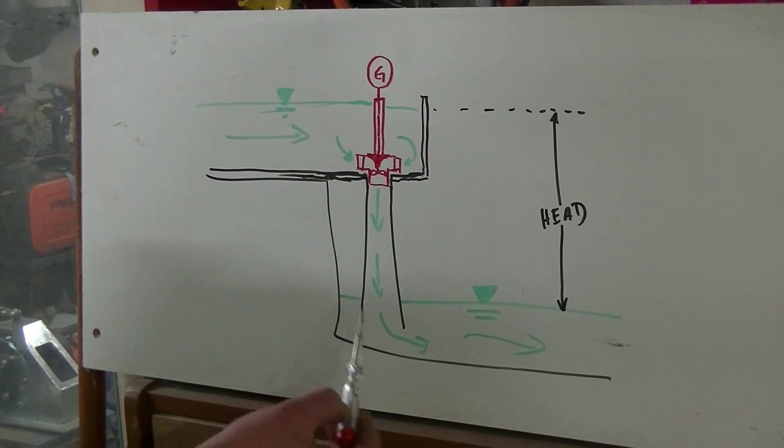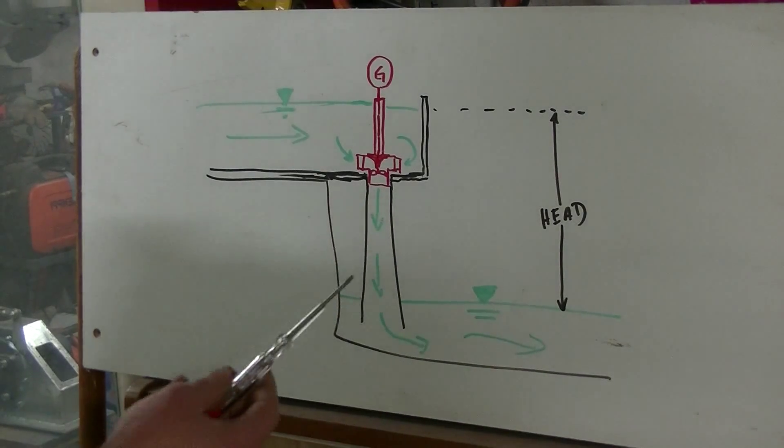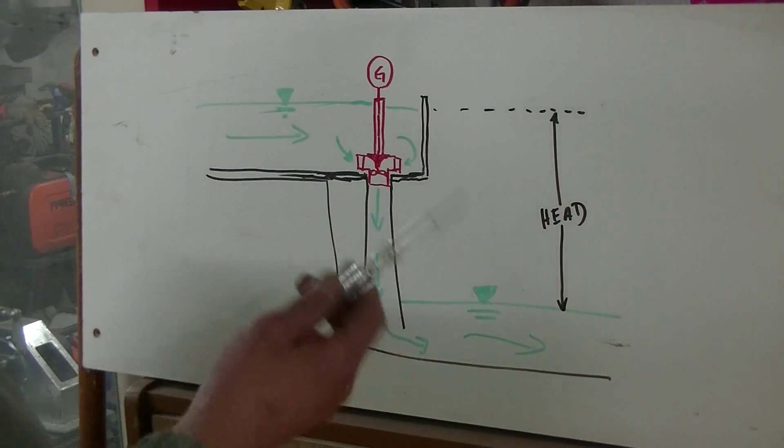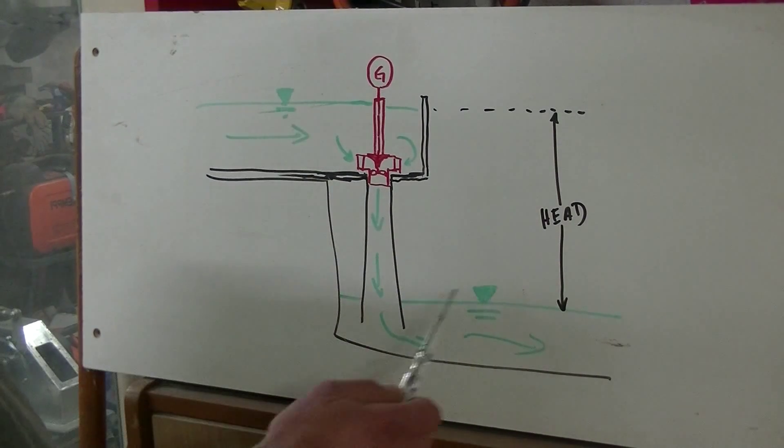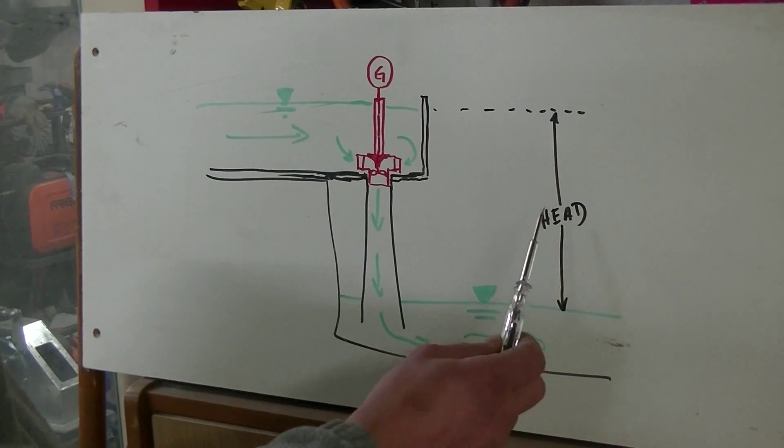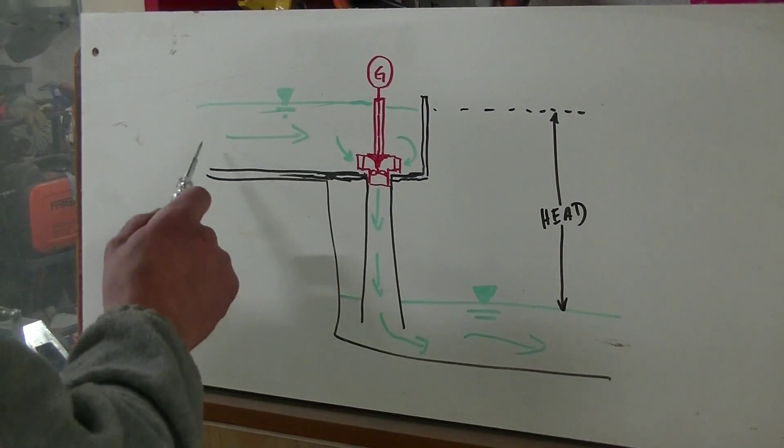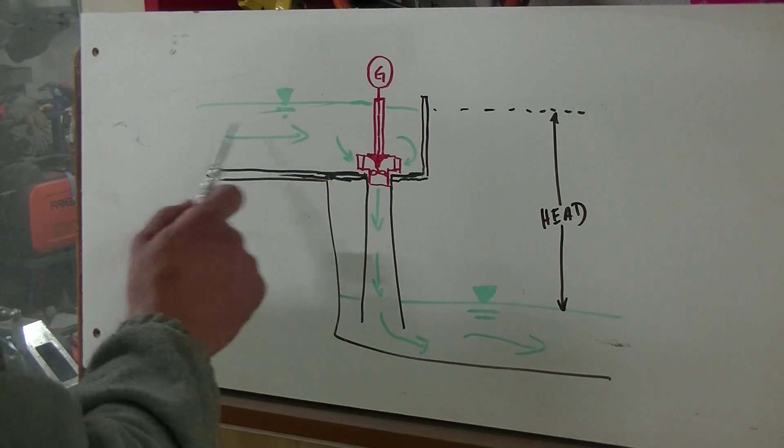In principle, it's very easy. Two important things for all hydro turbines are the difference between the higher and lower level, called the head, and the amount of water flowing or available on your river or stream, called the discharge in liters per second.